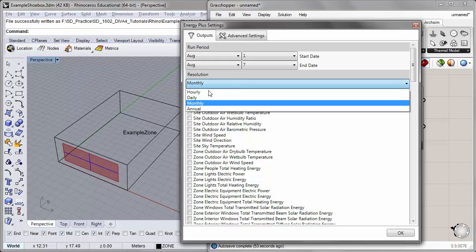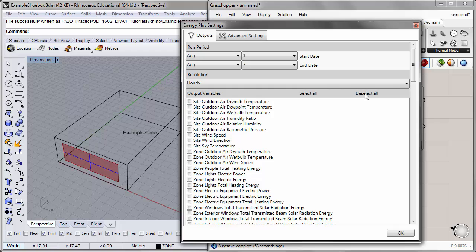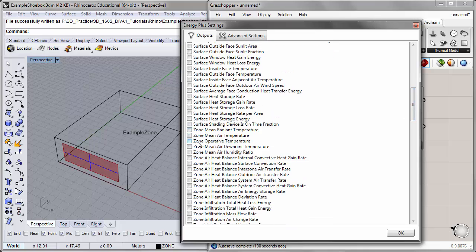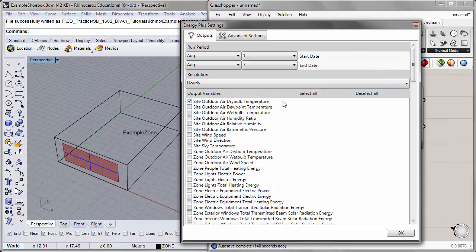Then let's change the resolution to hourly. We can deselect the output variables that we had previously selected and reselect the variables for this particular simulation. For this simulation we want the outdoor temperature for this specific Boston climate during this week, so I'll click on the site outdoor air dry bulb temperature. Then I'll scroll down to zone operative temperature, which is a function of the air temperature and the mean radiant temperature in the space, also considering wind speed. This will give us an interior zone operative temperature to compare to the site outdoor air temperature.